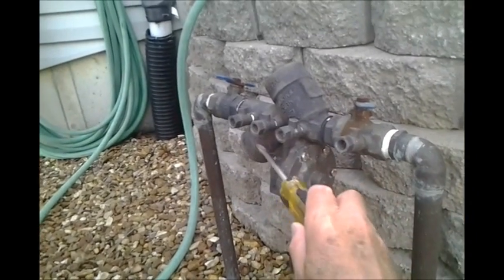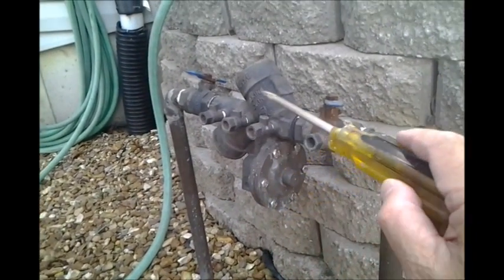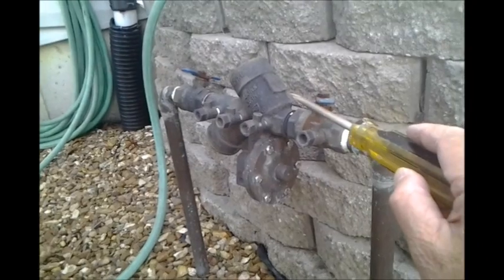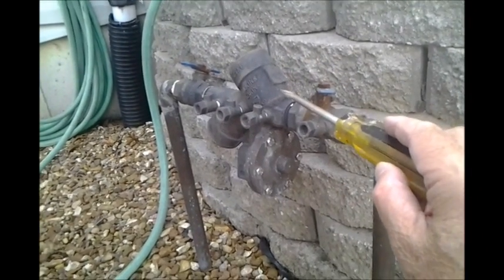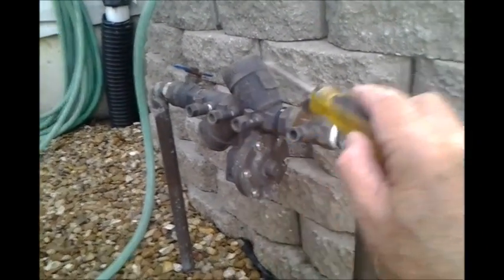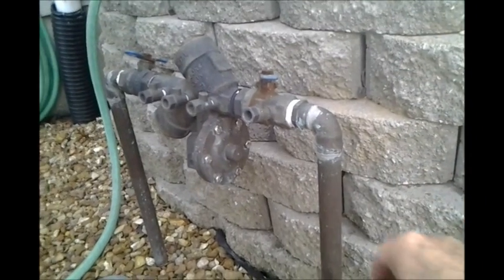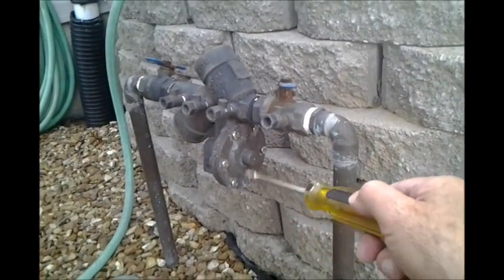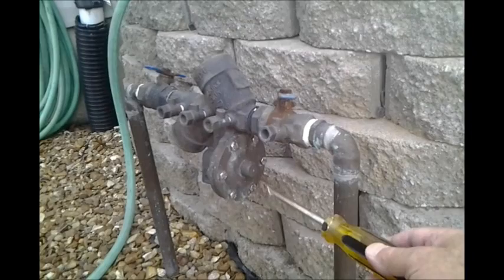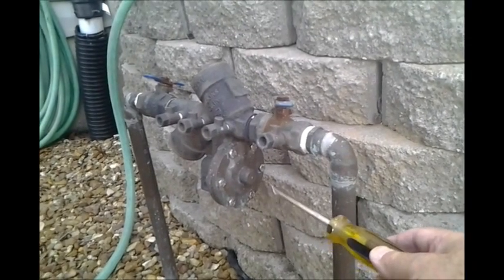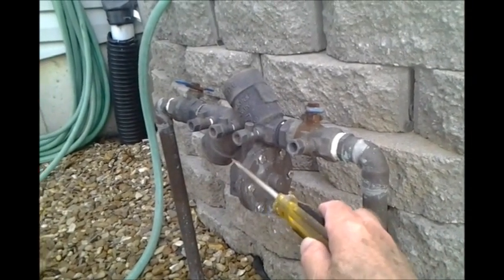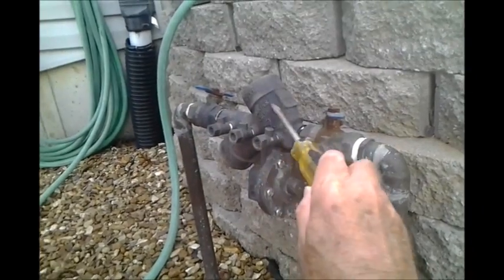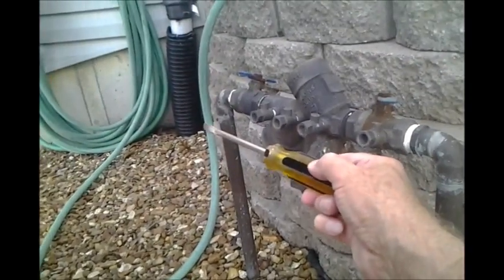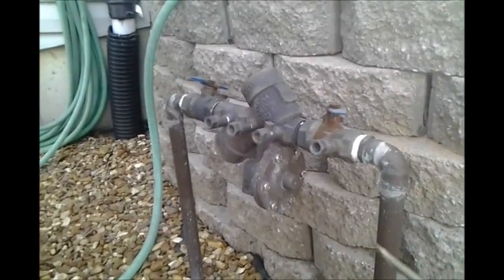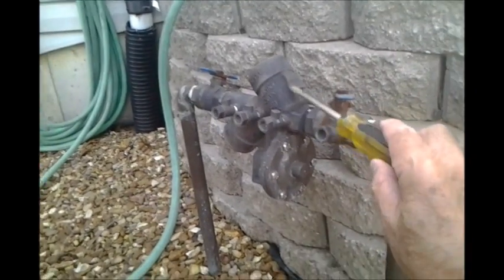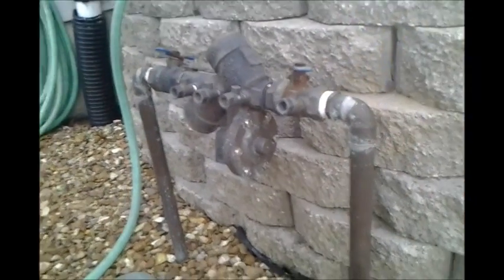This is a check valve to protect against a water main break where the pressure in the water main goes to zero. You don't want to siphon anything from the house, like a hose down into a laundry sink with dirty water in it - that's called a cross connection. This check valve only allows flow to go one way and not back. These should be tested periodically also.